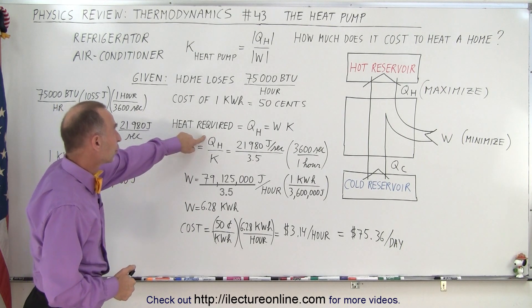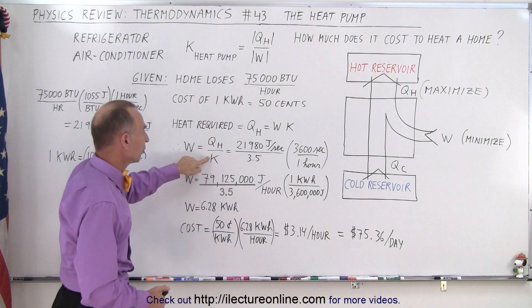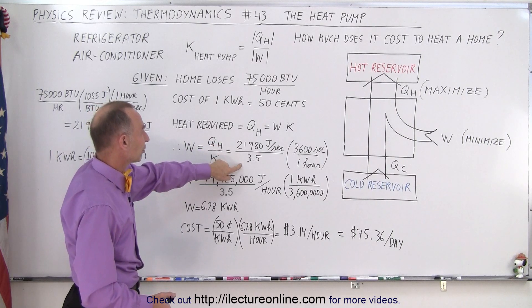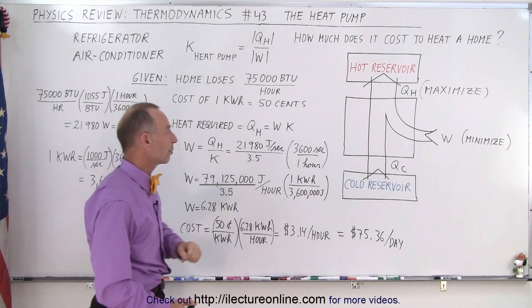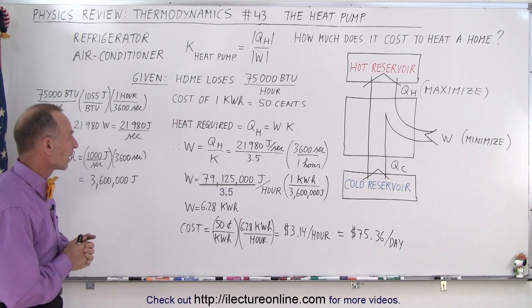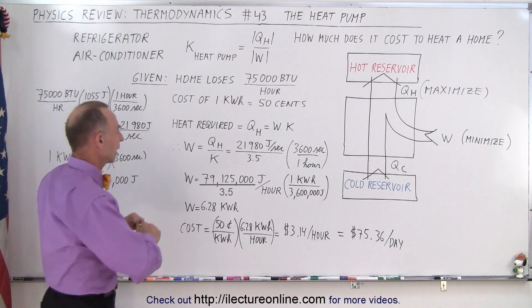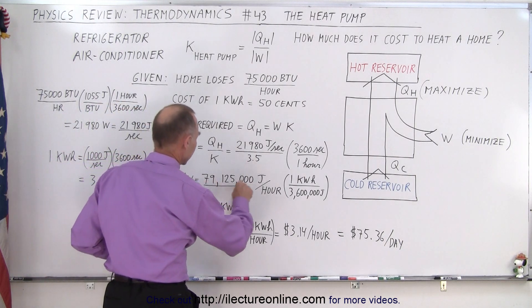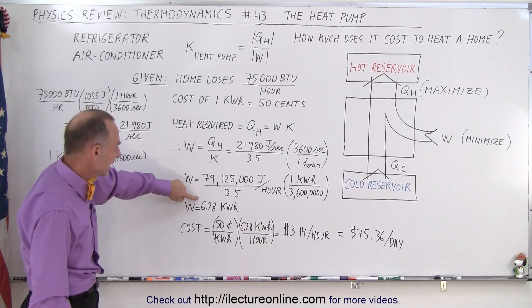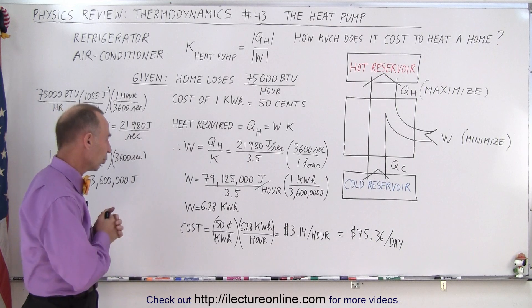So the work required is Q_hot divided by K. Q_hot is the heat we need, and K is the coefficient of performance. So we need 22,000 joules per second, and the coefficient of performance is 3.5. Then we multiply by 3,600 seconds per hour, because we want to know how much heat we need per hour. Dividing by 3.5, we end up needing 6.28 kilowatt hours per hour to keep the house warm.